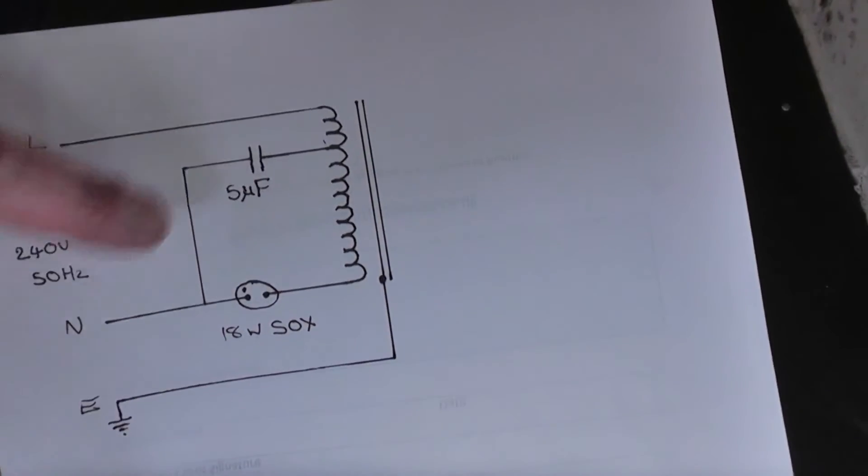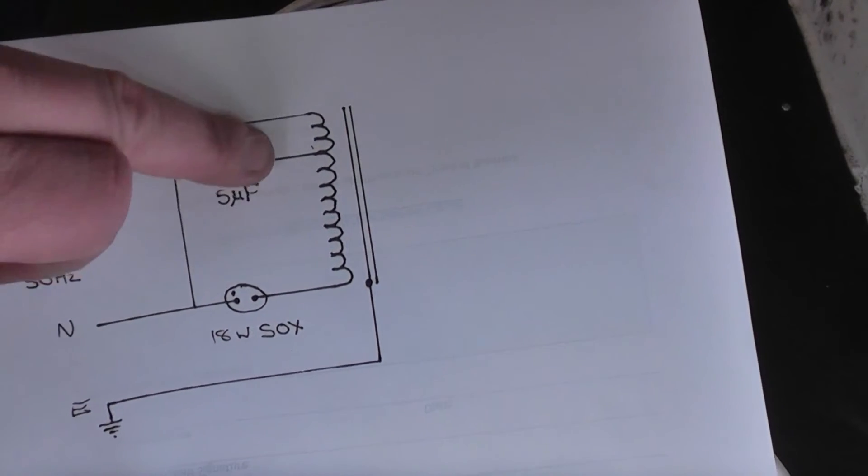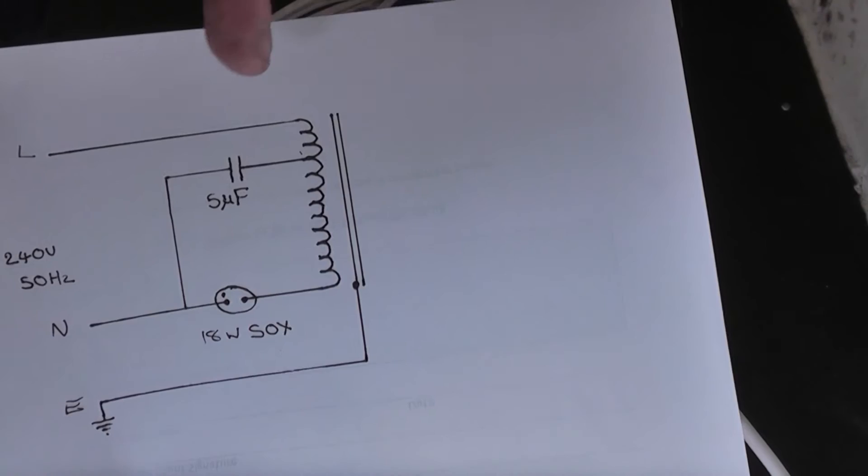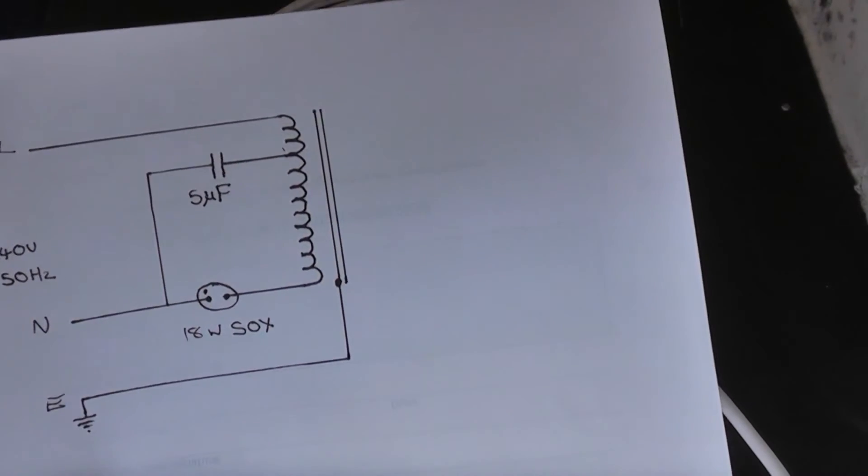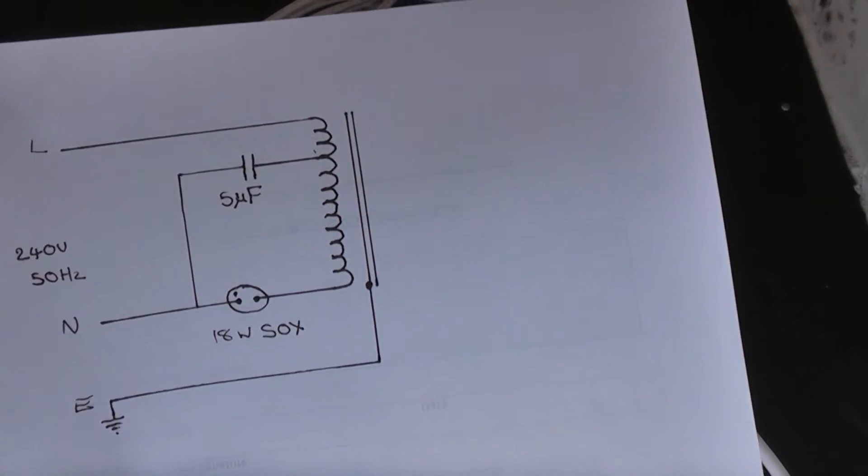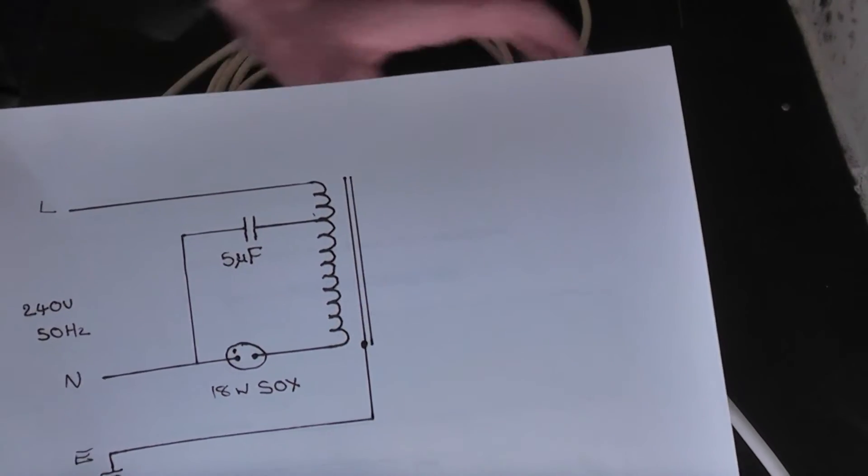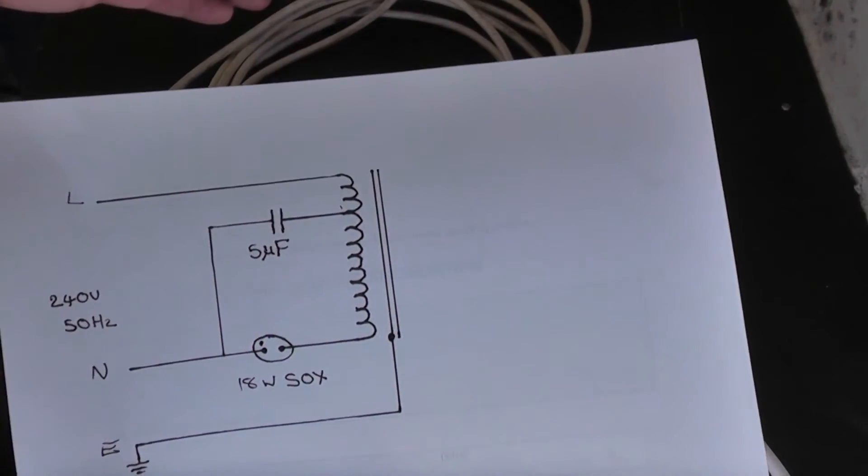So the neutral and the live are actually completing a circuit through this capacitor through these few turns on the ballast. So this is actually acting as an auto transformer which steps the voltage up to a couple of thousand volts which is enough to ionise the low pressure gas mixture inside.